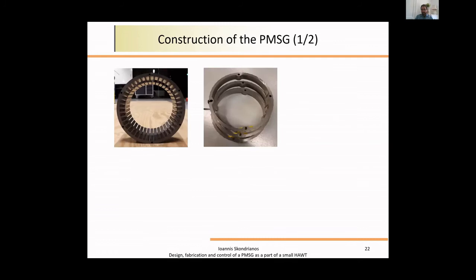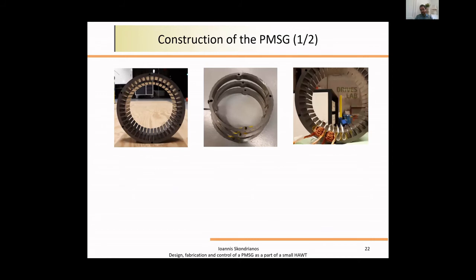Let's go to the fun part, the construction. The left picture depicts the stator laminations and the right picture depicts the rotor. These were not made at DTU, they were ordered. You can see the rotor comes in three different pieces because of the skewing process we discussed before. Here's the first step of winding the stator. You can see in each slot there are two types of insulation introduced. The yellow one is cotton tape and the white one is Nomex paper. That was very important to make the copper wires not touch the housing of the machine.